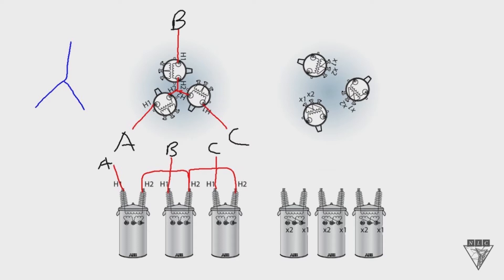So with a Y connection, you're doing a phase to ground connection. With the transformers, you have to have a potential difference across the coil in order for it to work. And there's one of two ways to do this: either a phase to phase connection or a phase to ground, like we're doing here with a Y connection.